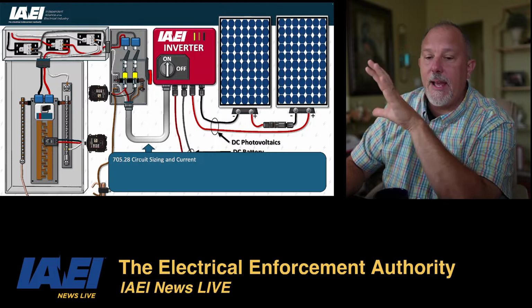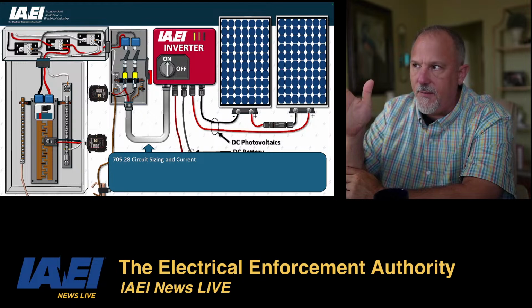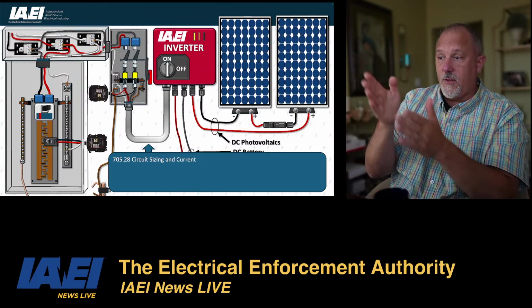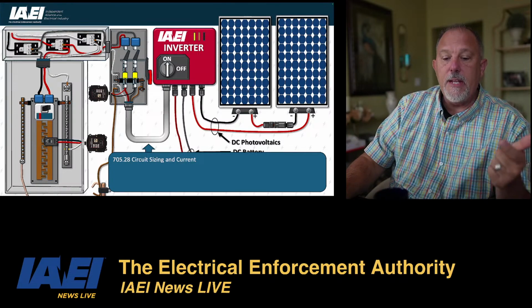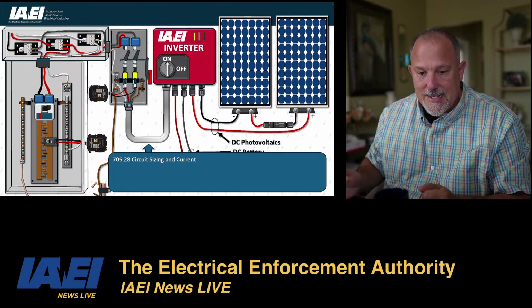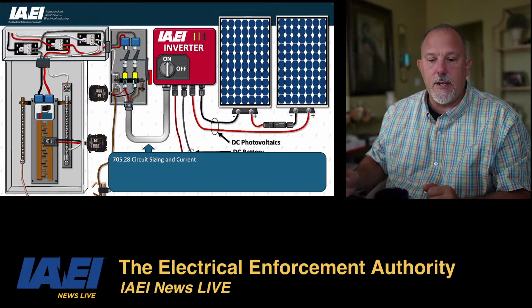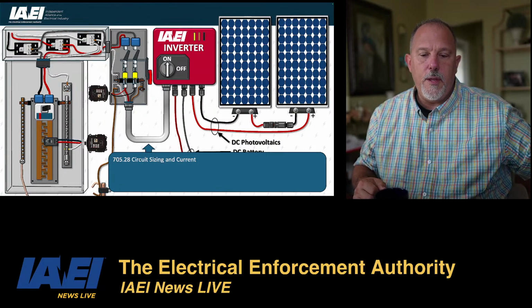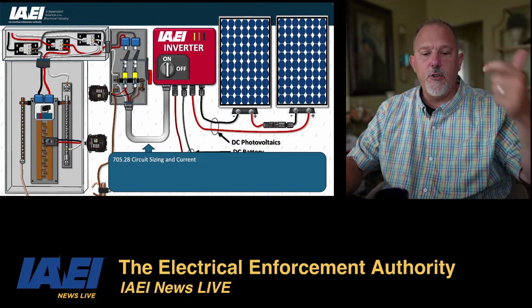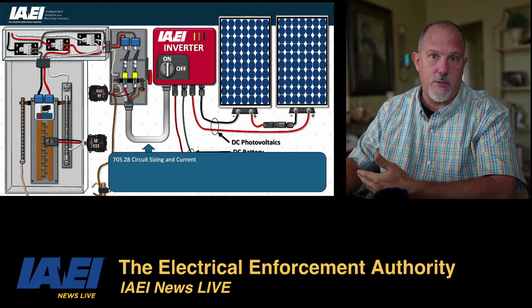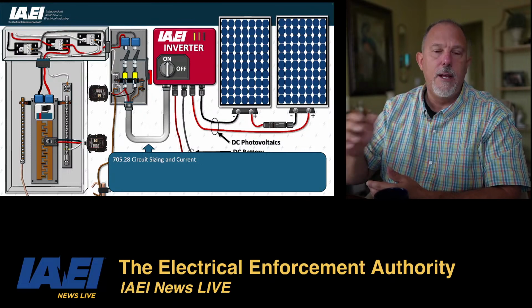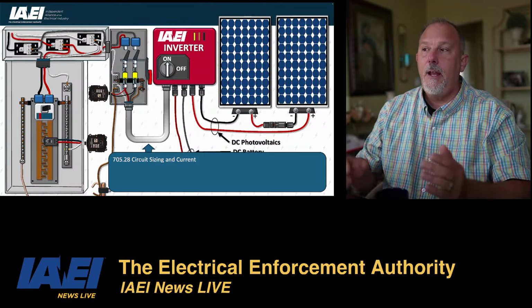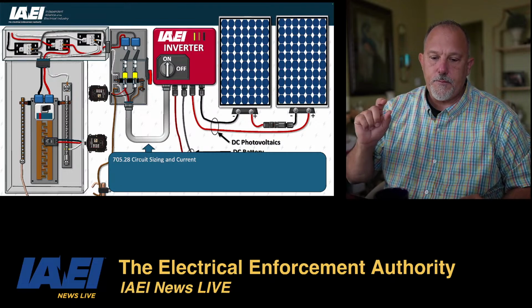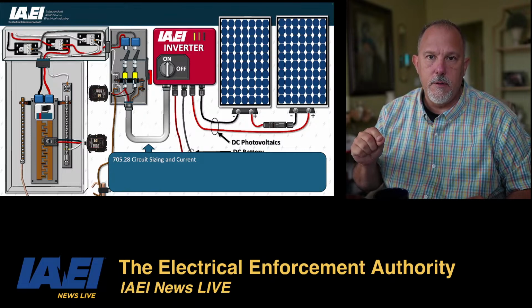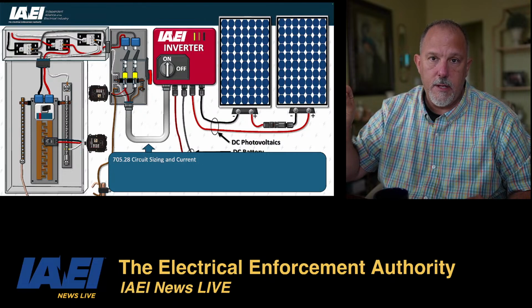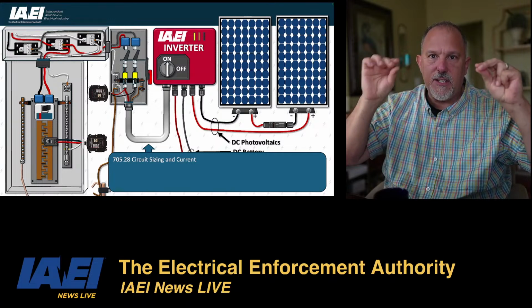I was going to say, so I have to calculate the maximum current that is capable of being delivered to the infrastructure through those conductors, and that's in 705.28(A). In 705.28(B), I calculate my conductor ampacity, and what this does is it takes my maximum current, and I do the same thing we do in branch circuits and feeders. We do two calculations. We calculate the maximum current. We do the 125% for the continuous loads without adjustment and correction factors. So if I have multiple conductors, or temperature correction factors, all that jazz, I forget about all of those. I do the 125% times that maximum current, and I get that size conductor. Then I do another calculation. I apply all of the adjustment and correction factors, and I don't apply the 125%, and I get that number. And then I make sure that my conductor size is the larger of the two.